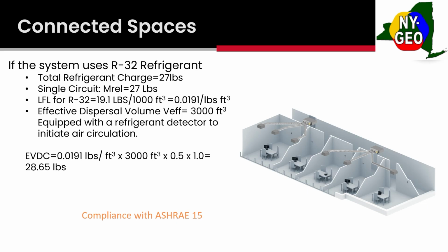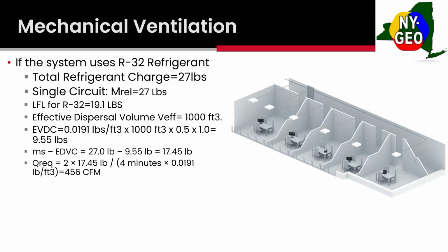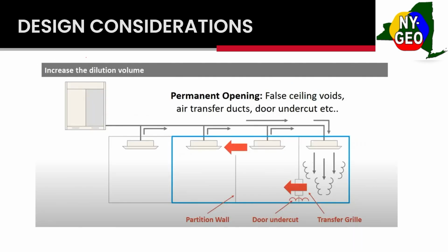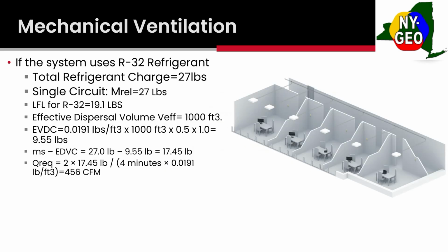So, a quick calculation here. By combining this, our EVDC is 28.65, just over our releasable charge. So we are in compliance with ASHRAE 15. Again, we're connecting spaces to increase our volume. Mechanical ventilation, this is kind of a funky example because I don't think anybody would put mechanical ventilation in an office, but this is just to show you what would be required. So in this little space here, you need 456 CFM of ventilation.